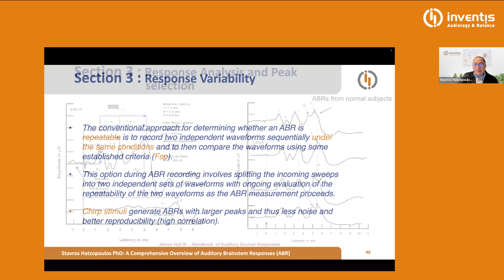It's called FSP. So as you are collecting data, you reach a moment where your FSP is telling you, okay, stop. With the automated ABR, you don't even have to control this. The device does it by its own. In clinical recordings, many times, if the FSP is not high enough, that is above 3, we might do the recording again. Why is it important to have good quality responses? We know that, and this is why it is very common to use the chirp stimuli in order to get the maximum signal noise ratio out of these responses.